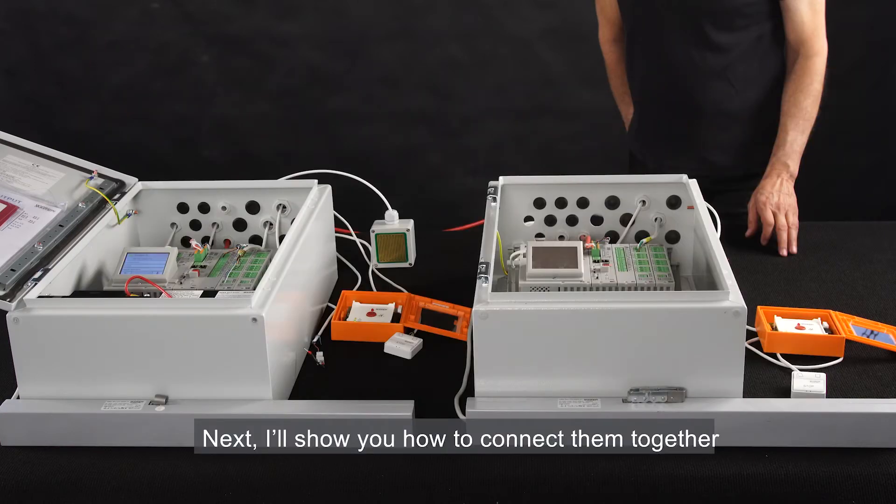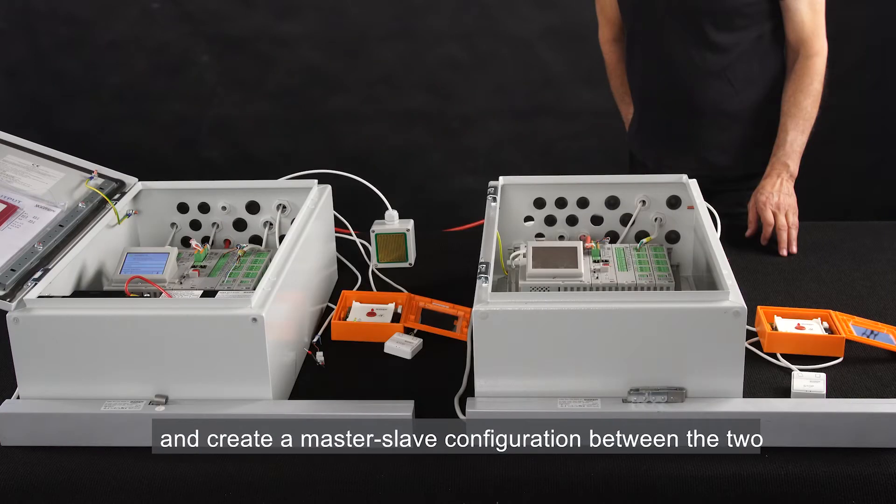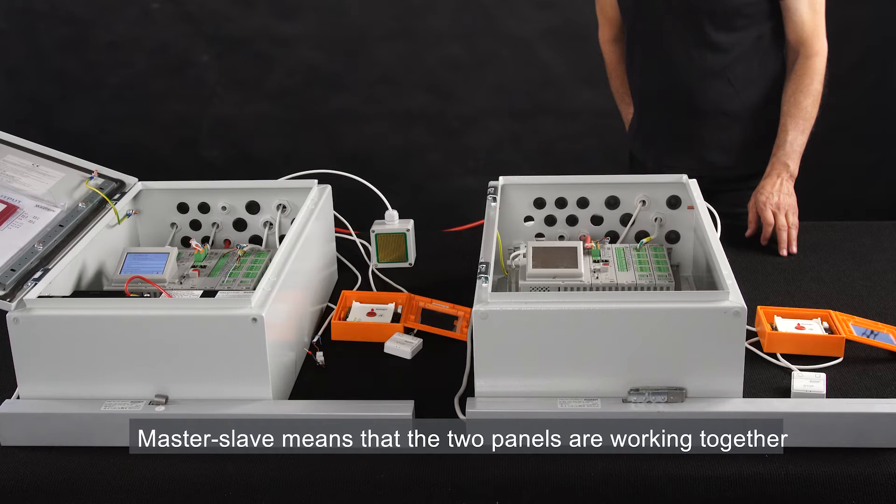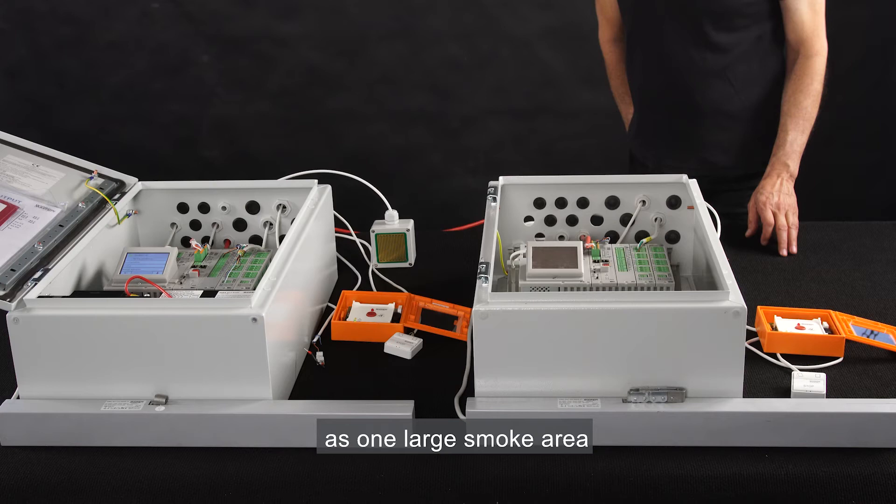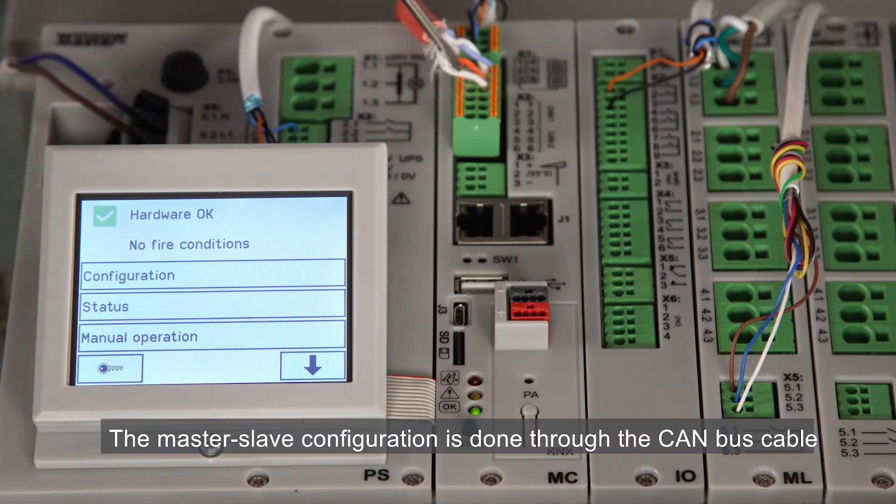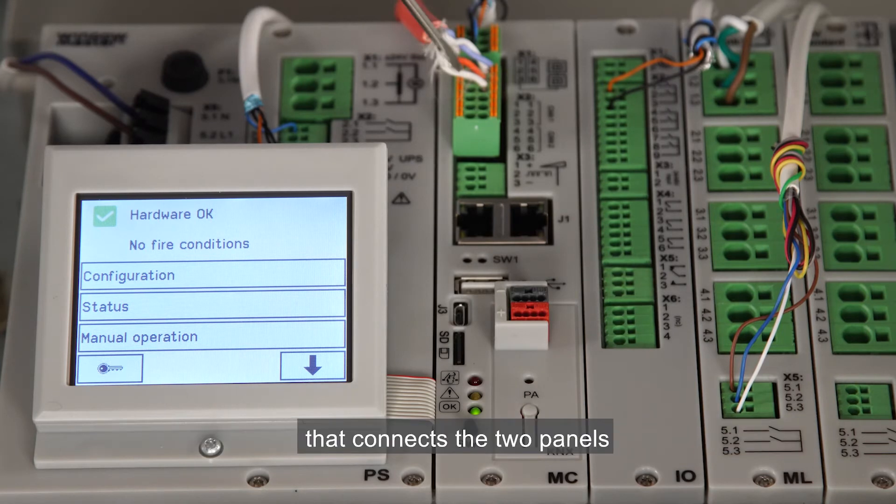Next, I'll show you how to connect them together and create a master-slave configuration between the two. Master-slave means that the two panels are working together as one large smoke area. The master-slave configuration is done through the CAN bus cable that connects the two panels.